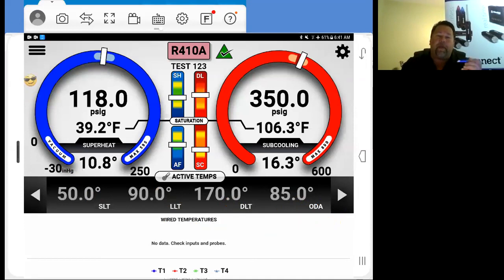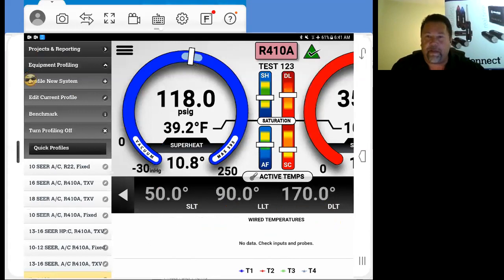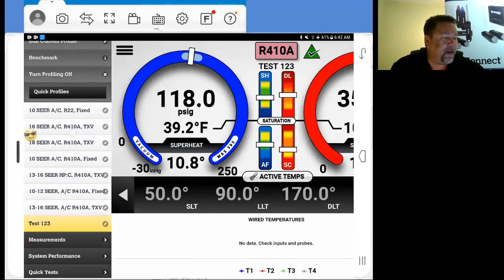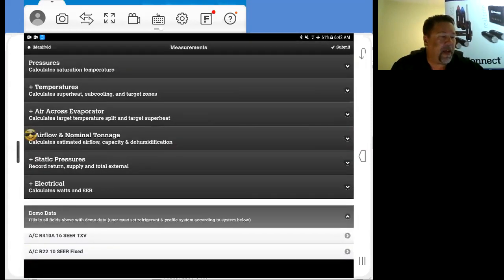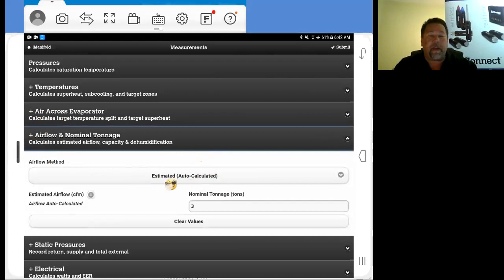We're going to take a look and enter our tonnage so we can get our airflow. So, based off the information on the system, I'm going to go back in here down to measurements. Open up our measurements tab. We can take a look at our pressures, our temperatures, air across the evaporator. That's what our 911Ms are picking up. Airflow and nominal tonnage. Now this is where we're going to have to enter in our tonnage. Open up that tab. Our airflow method is estimated, auto-calculated. That's with your 911Ms and a profile.